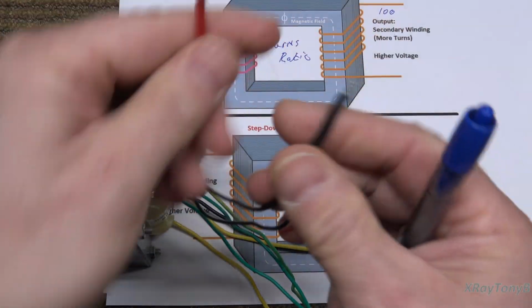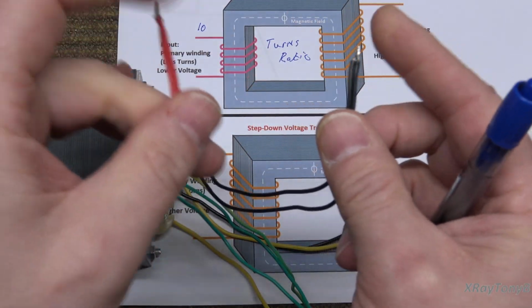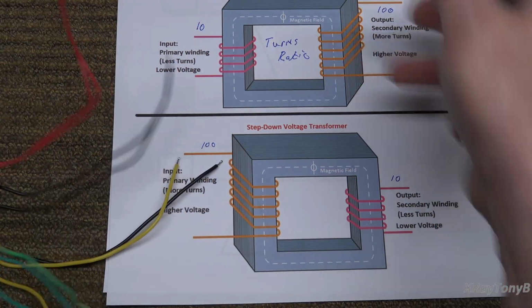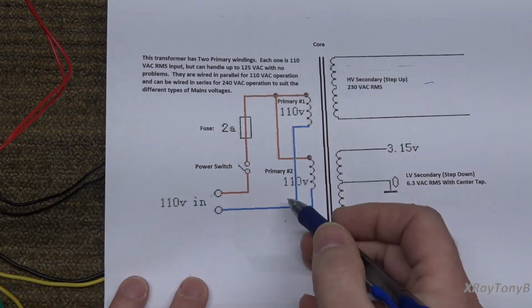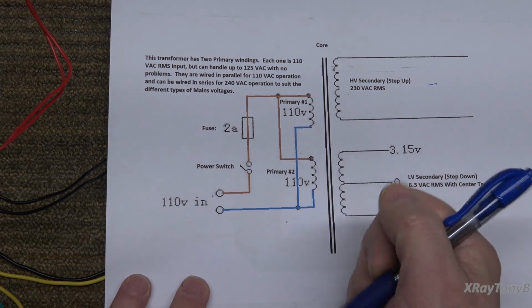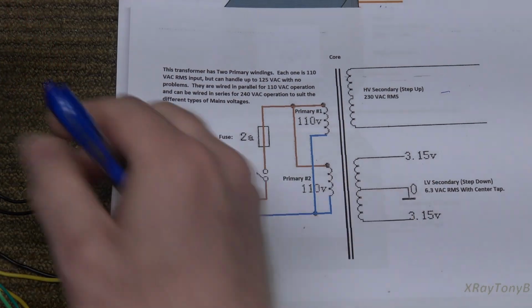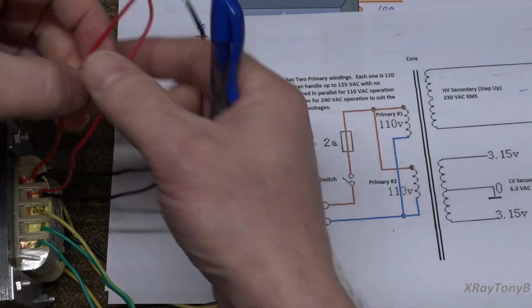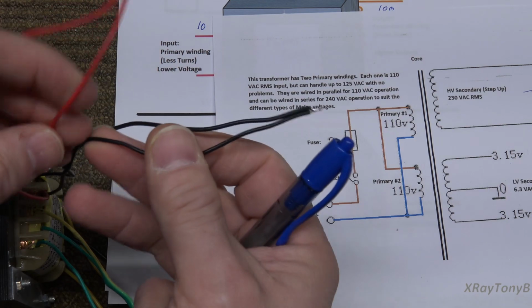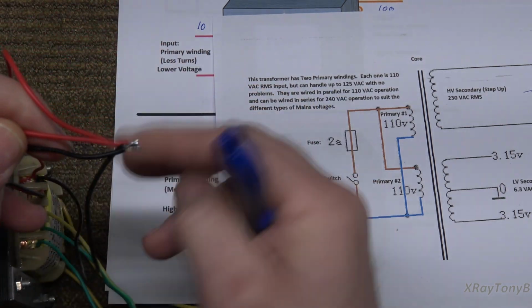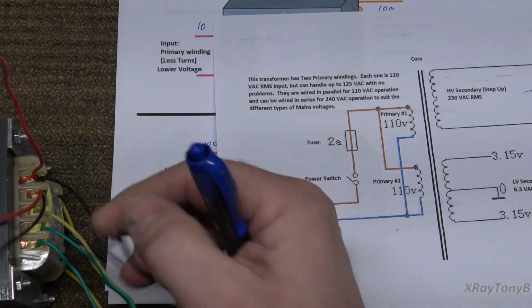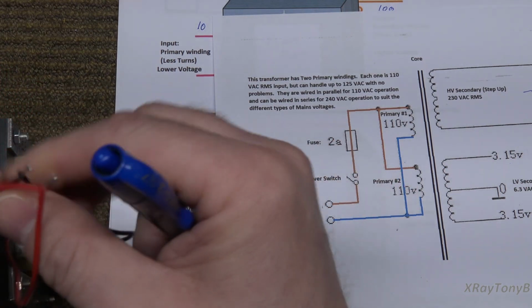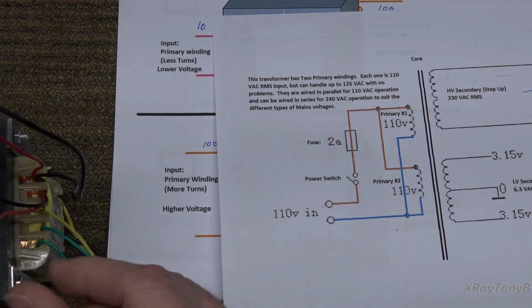These are our primary windings, and if we wire the two black wires together and the two red wires together, that puts those two primary windings in parallel, just like on our schematic. If we wanted to wire them in series instead, I would take one of the red wires, disconnect it, and connect it to one of the black wires like this. They would be connected together, and then the other black wire and the other red wire would be your inputs, if that makes sense.